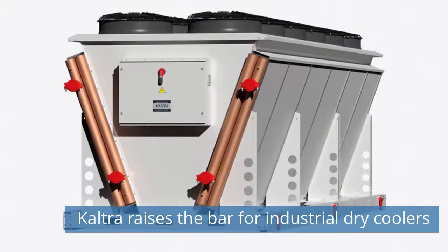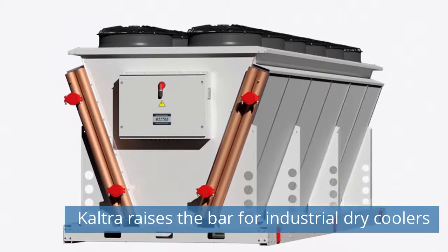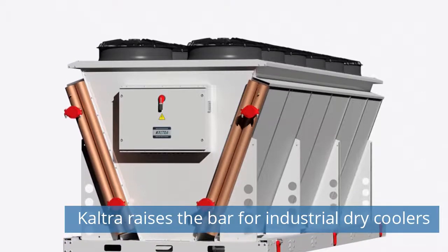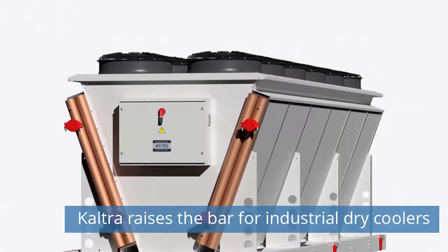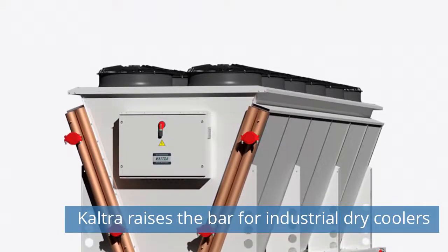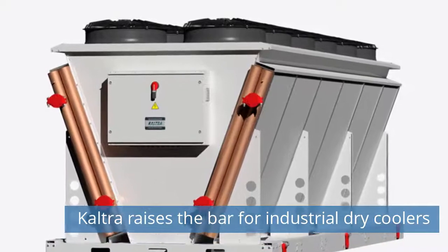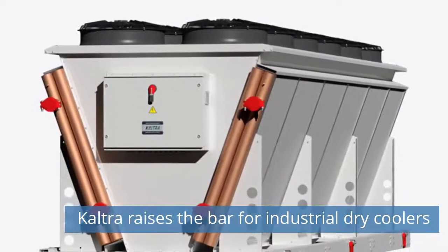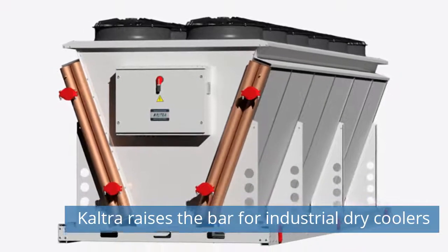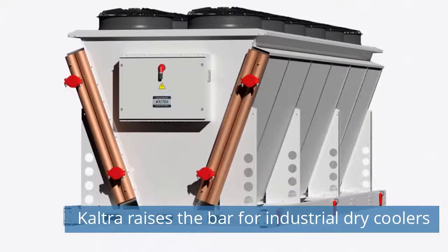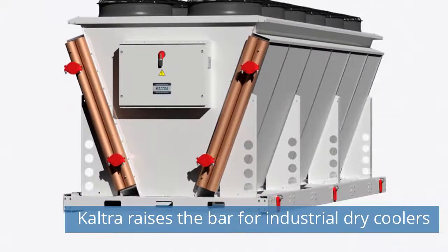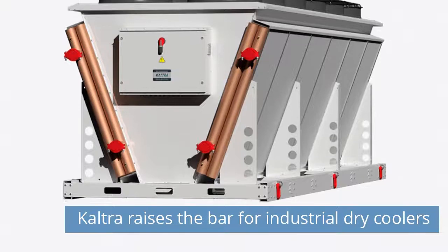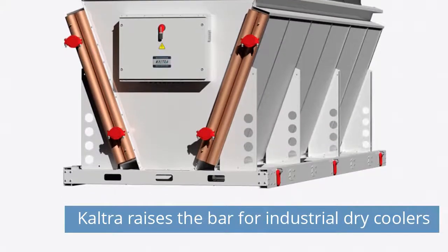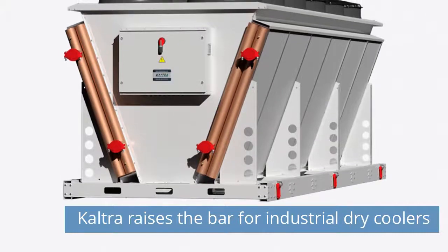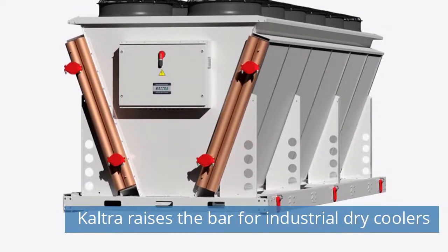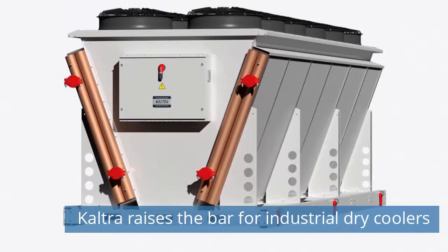Inner grooved copper tubes of small diameter contribute to a cooling density of 75 kilowatts per square meter and higher. At the same time, airside fins with unique profiles create a low pressure drop, enabling lower fan energy use and maintaining moderate noise levels. For sensitive applications, Kaltra made available heat exchangers with stainless steel pipes and a selection of fin materials: aluminum, magnesium alloys, and copper. Mistral dry coolers have been developed for cooling applications in the oil and gas, chemical, petrochemical, power generation, and food processing industries. Their corrosion-resistant, robust, and easily serviceable design contributes to long operating life even in harsh environmental conditions.